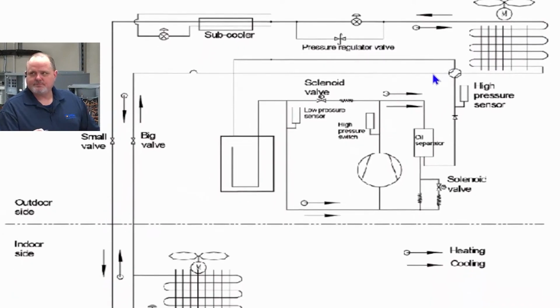stored in the condenser coil. So part of the reason why I'm bringing this up is because a lot of troubleshooting that guys call us about can be easily answered just by doing some simple inspection. This was actually, the call I'm talking about was the fault of GREE. It was not the installer's issue at all. The solenoid valve on this EEV was dangling in the unit. It wasn't even on the armature of the EEV, so there's no way the motor could actually open the EEV. So this was 100% closed and pumping me down.